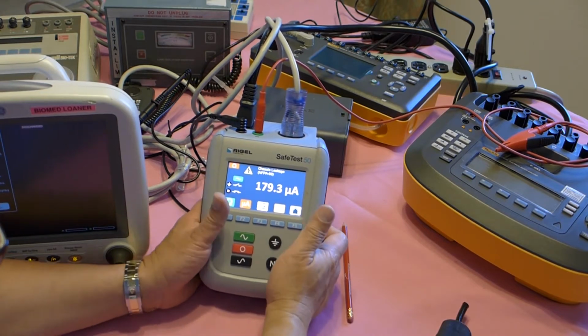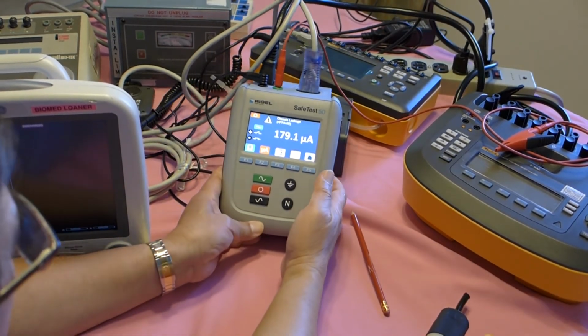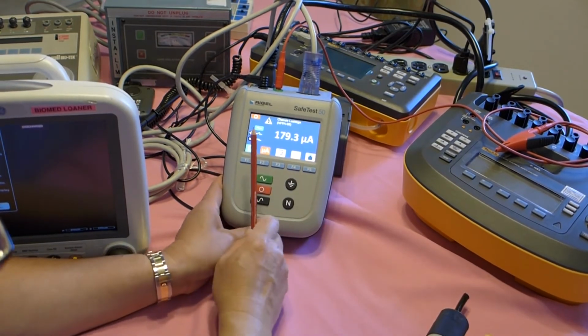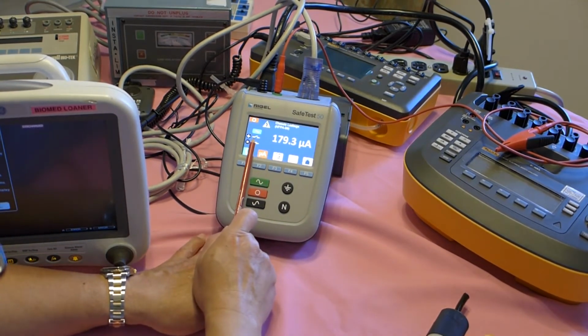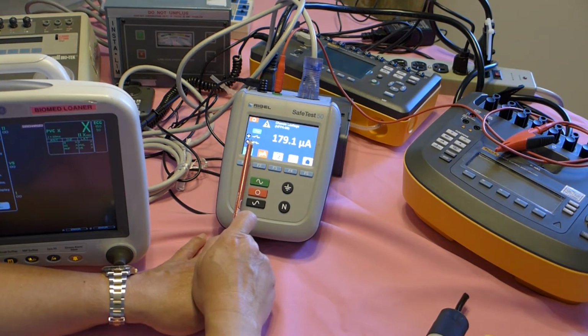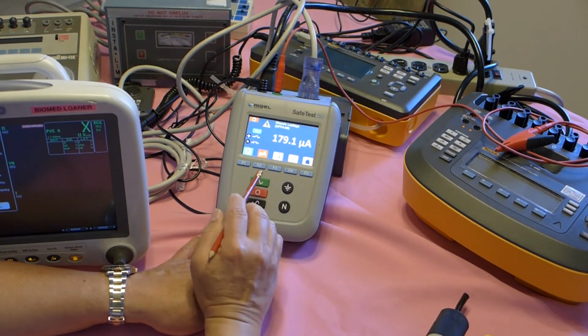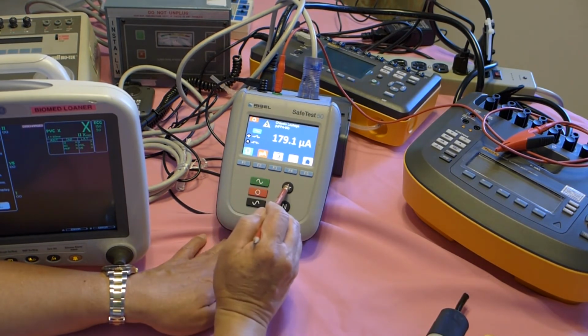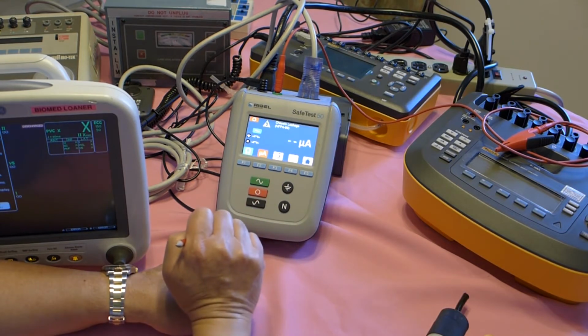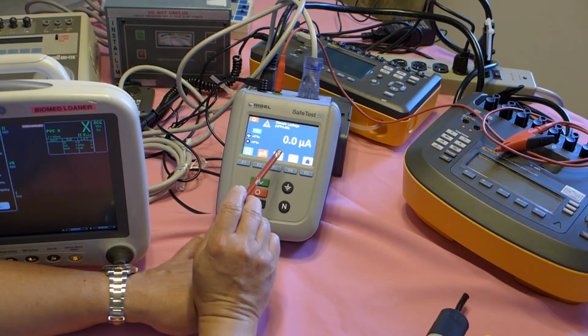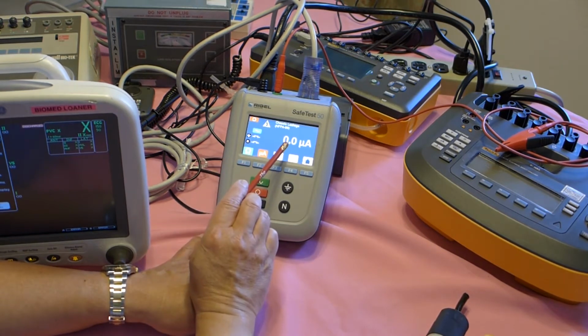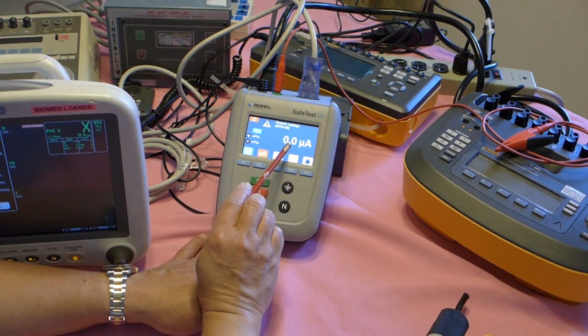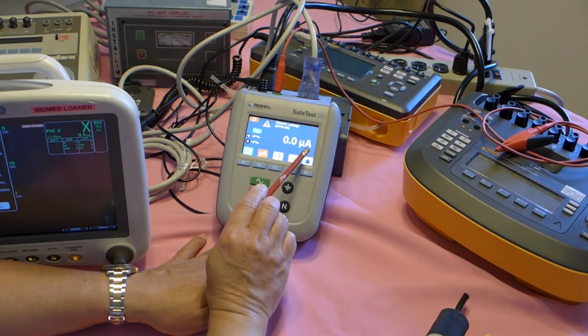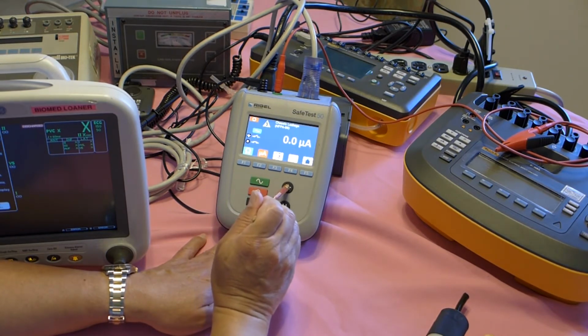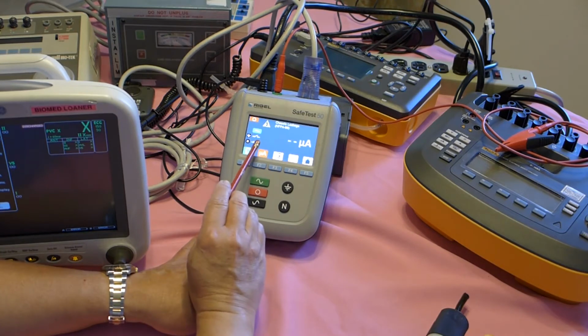Okay, now this is okay. This is supposed to be open grounds. Normally, what we're testing here, we want to create the worst case scenario that has the open ground. So what we're expecting is if you have a good ground, it should read at 0.0. That is a good ground. It will have zero leakage. If open ground, that's what you should read.